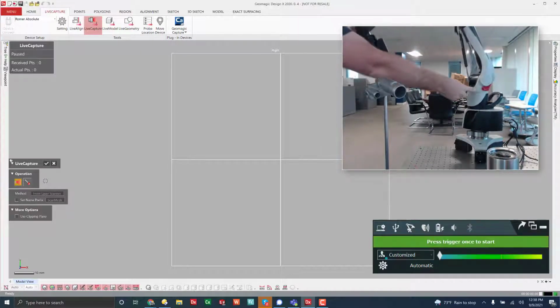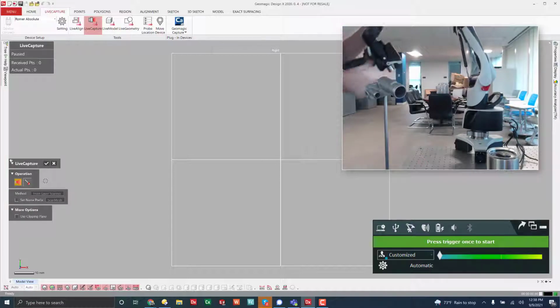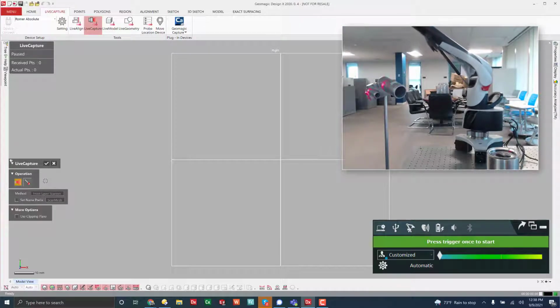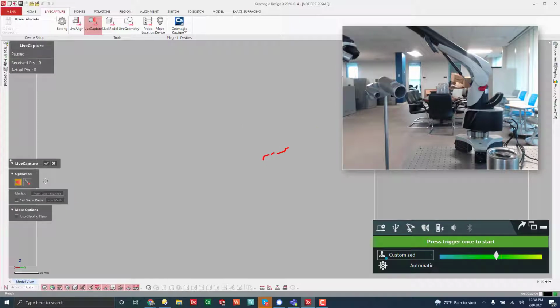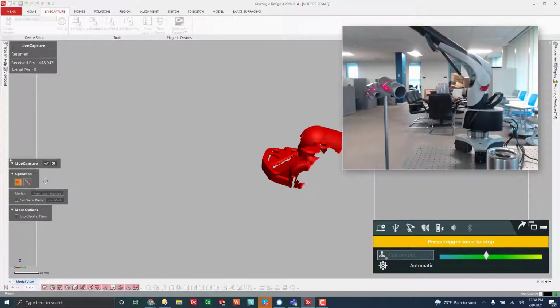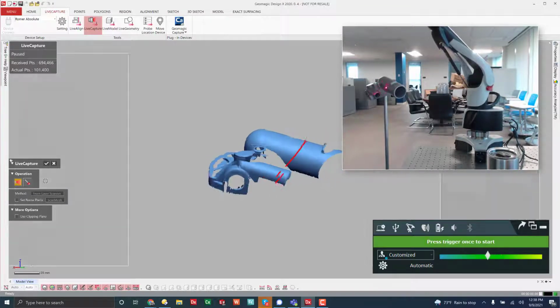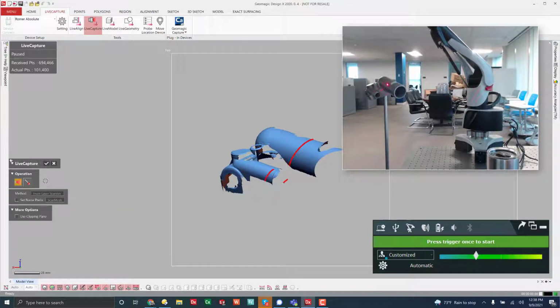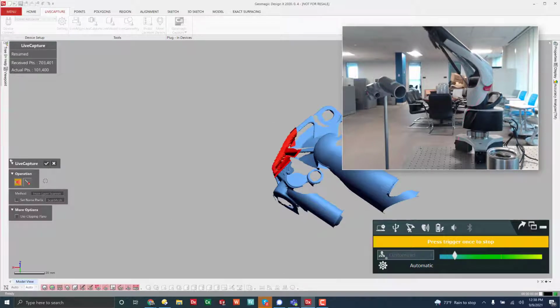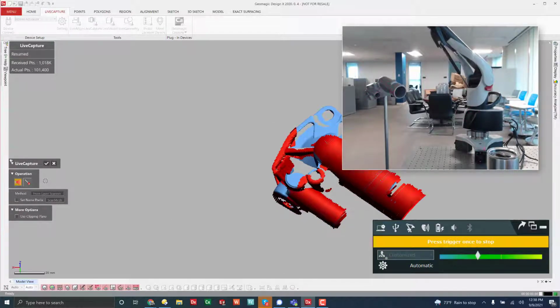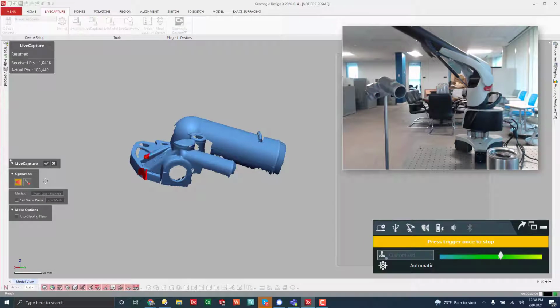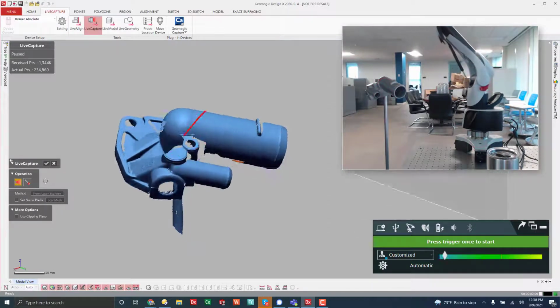So I'll grab it. Make sure this lock isn't on, because that lock will allow you to bring the laser down. You'll get this noise here when you're capturing data. Another thing that you can see is there is a dot and a laser. So you want to make sure the dot and the laser are close to each other. It's basically to show you your depth of field, so you know how far away to put the laser from the part itself.